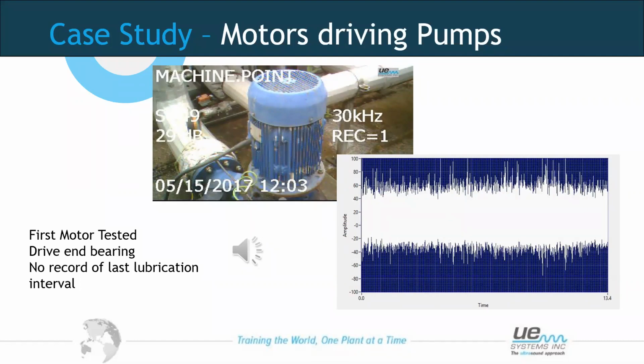Again, if we've got a good baseline and we understand what we're listening for, if we have damage to the impellers or the rings inside, it's going to change the ultrasonic emission. It's not necessarily going to tell us that we have impeller wear or the rings are wearing, but it's going to tell us something has changed, and not for the good, if we have good baselines.